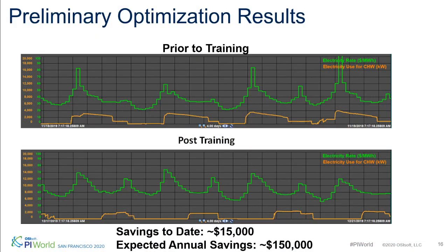I mean, you can see, it looks to me like between the second spike to the right and the third spike to the right, they've actually maybe gone for 2 days. I need to think about this. Oh, maybe not. I think they've at times been able to actually go for 2 days without running the chillers when needed. The power of putting data in front of operators. Oh, that's very cool.